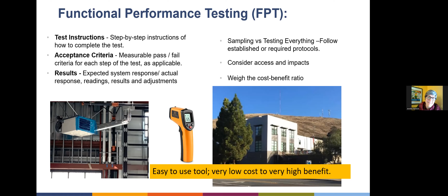Testing for all functionality. And this even includes acceptance testing protocols for exhaust fans in the bathrooms, especially if they're being used for introducing the outside air. Some of the questions answered during this process are: are these scheduled to be operational continuously or intermittently? Is it set strictly for bathroom use, where you flip it on when you need exhaust and otherwise it's off? Or if it's part of the outside air system, is it a balanced system? In other words, is there an outside supply air that makes up for that continuous exhaust? And are they interlocked properly? Are they connected with each other?